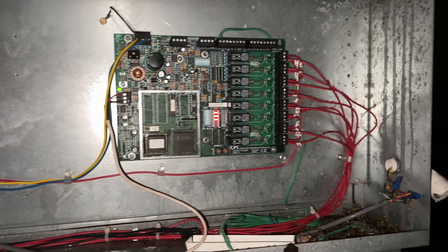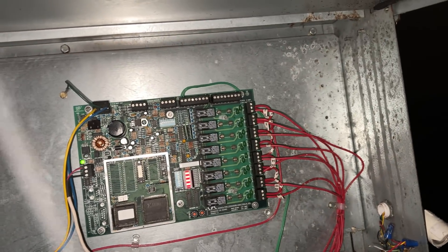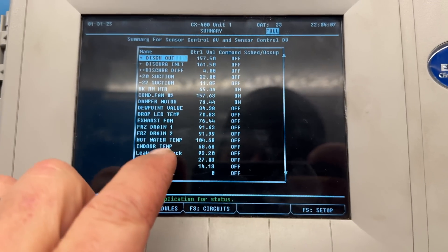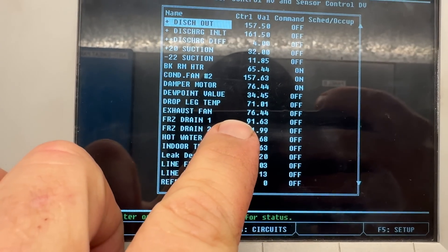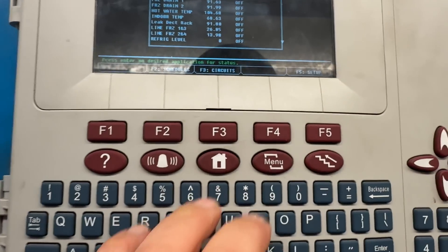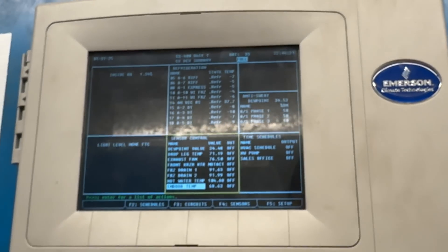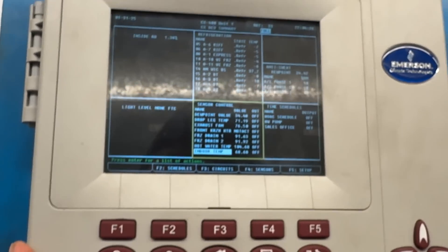Fans are starting to come on — they were all shut off a second ago. See your temperature sensor — that actually looks okay. There's some sensors here they have inputted in and they weren't quite right. This is looking better. Drop leg earlier was 38 degrees. We're out of alarm now. Imagine that. Let's do alternate in. Look at that — they're all online.